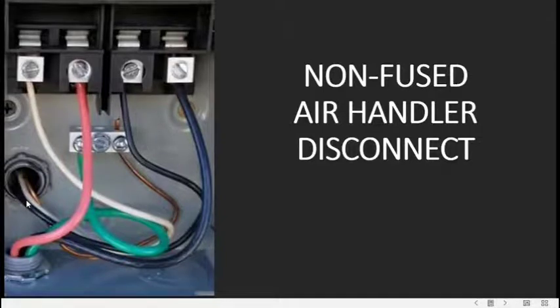We have your black, white, and your ground. Your ground doesn't have to be insulated like your 220 volts does. So from the breaker box, your black goes to this side, which is your line in, and your white is your line in, out to the air handling unit, your load, L1 and L2 of your load. In this particular illustration, this one is insulated. It goes to the ground, which in turn goes back to your breaker box.